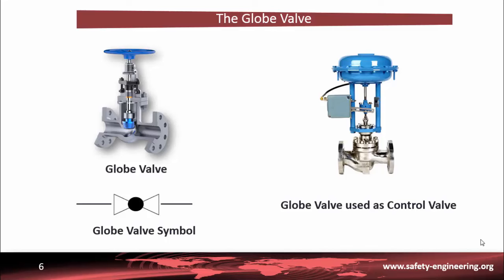A globe valve is a linear motion valve primarily designed to stop, start, and regulate flow. The disk of a globe valve can be totally removed from the flow path or can completely close it. Conventional globe valves may be used for isolation purposes, though they exhibit slightly higher pressure drops than gate, plug, or ball valves. Globe valves are especially used to control flow — when choosing this valve, one must look carefully at the range of flow control, the pressure drop, and the context in which the valve will operate. The gradual change in spacing between the disc and seat ring gives the globe valve good throttling ability. This linear motion valve can be used in a variety of applications as long as pressure and temperature limits are not exceeded and the process does not require special materials to combat corrosion.